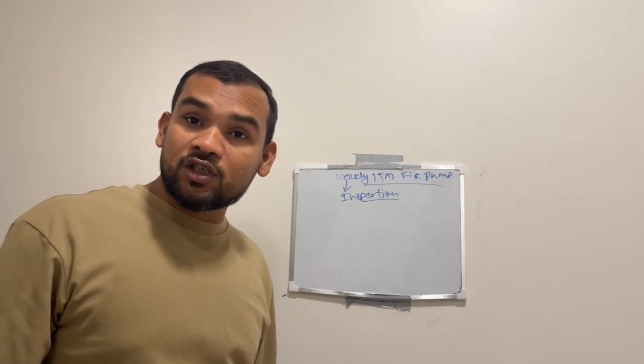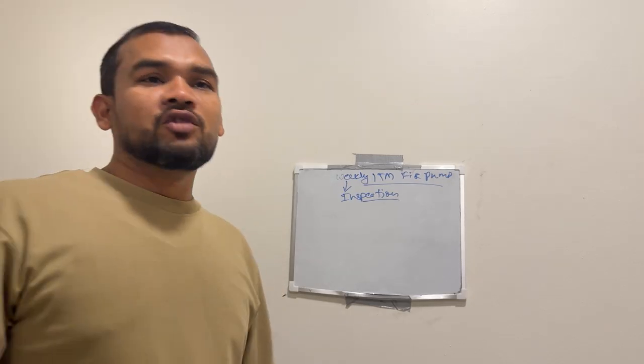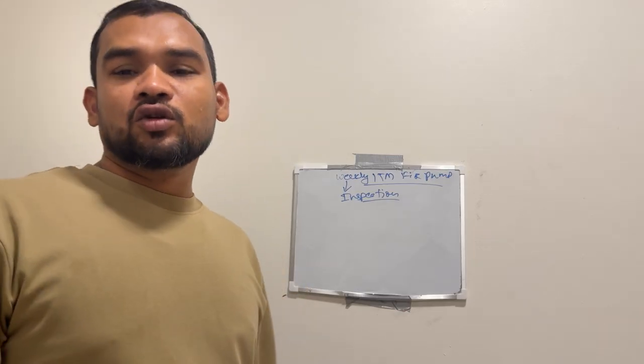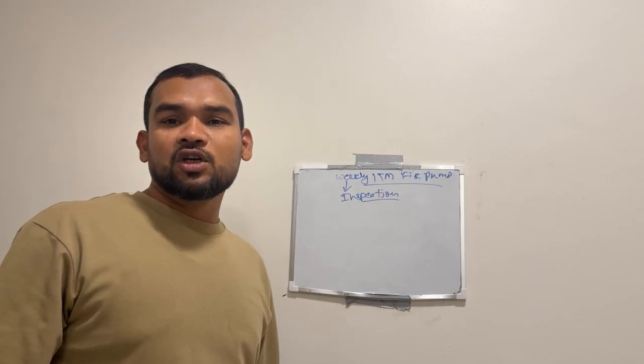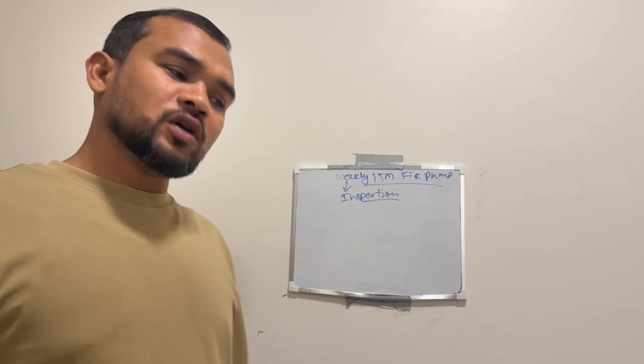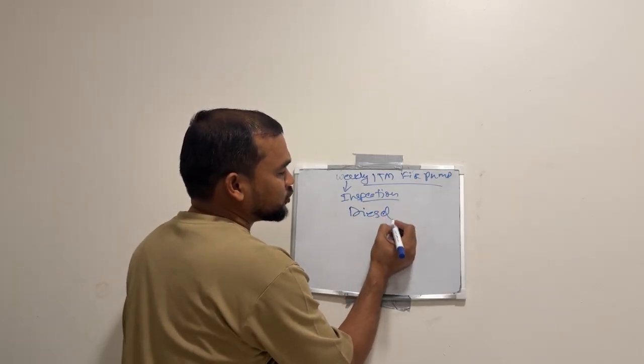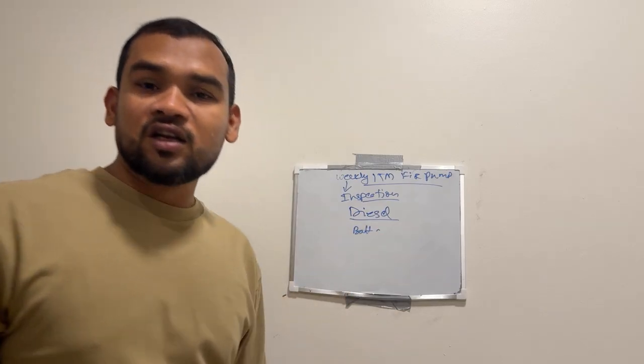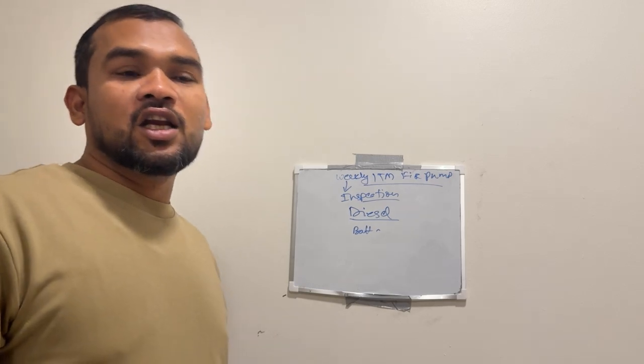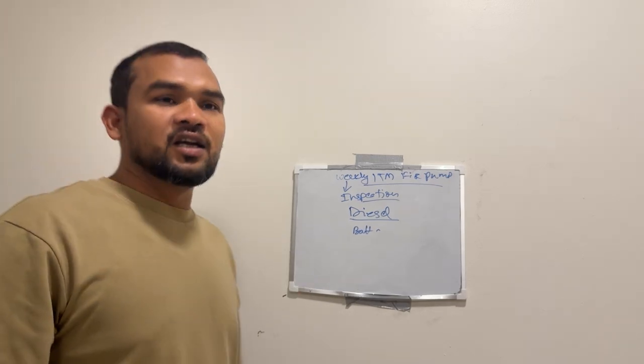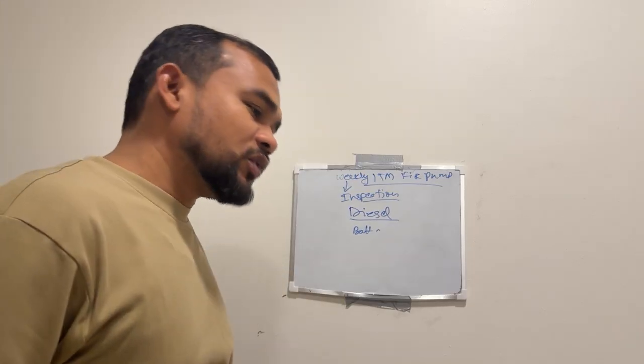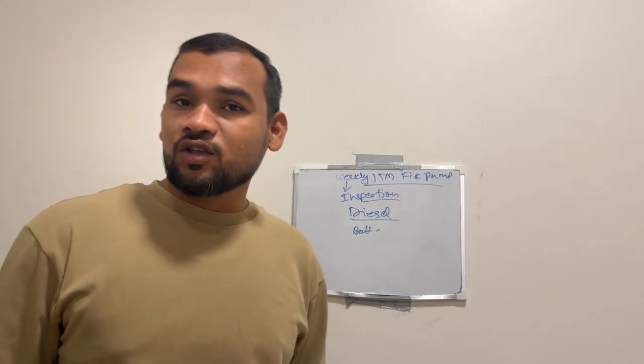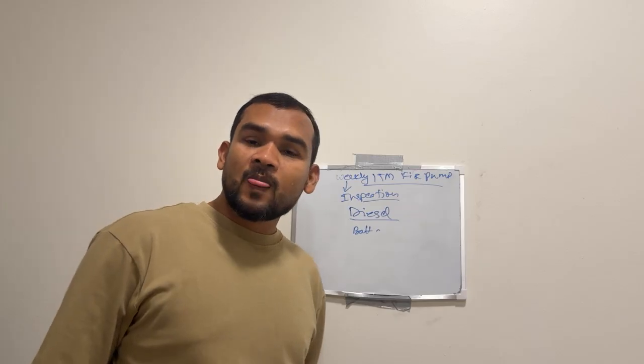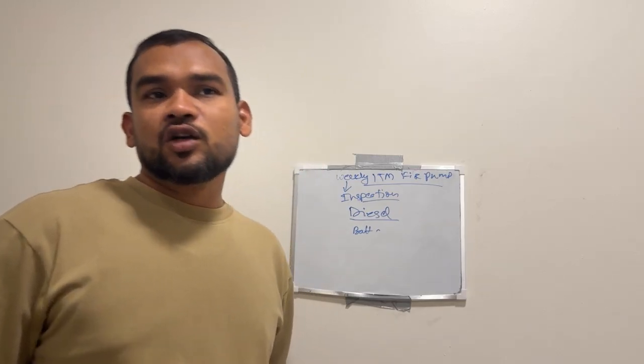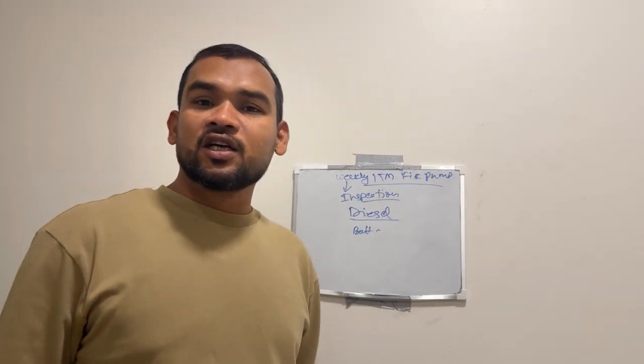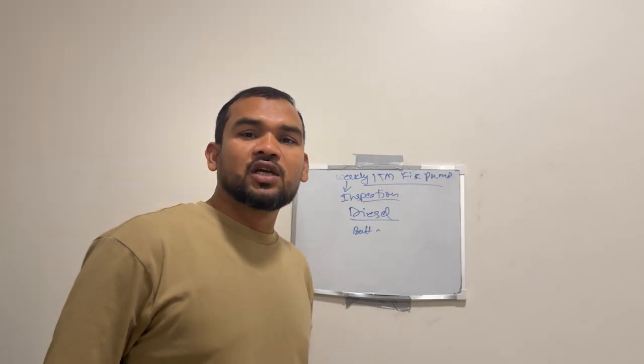We also have to check the transfer switch, whether the normal light is illuminated or not. We also check the selector switch is in auto position or not, because the selector switch should always be in automatic position. We also have to check the diesel engine side. We have to check the battery terminals are free from corrosion and the terminals are okay. Battery electrolyte levels are in acceptable range or not. Batteries are showing the correct voltage in acceptable range. Battery pilot light is on, battery failure light is off. And we also check the diesel engine tank level. It should be two-thirds of full. Controller switch on auto position. Battery charging current is okay, so the charger will be okay.